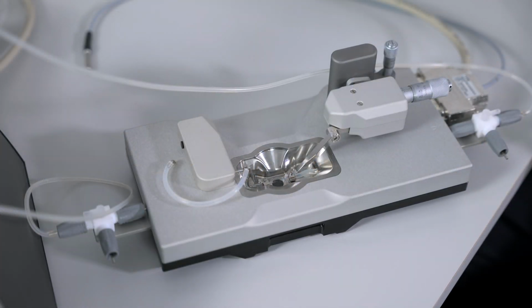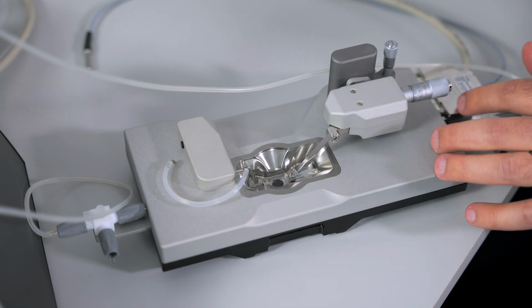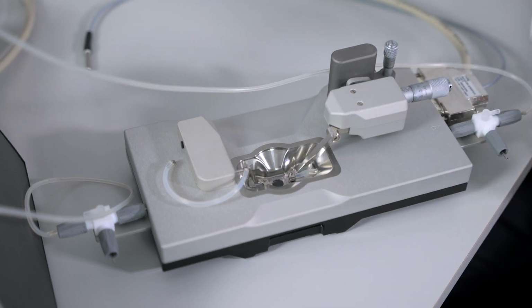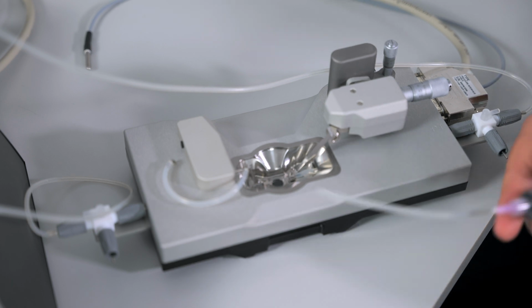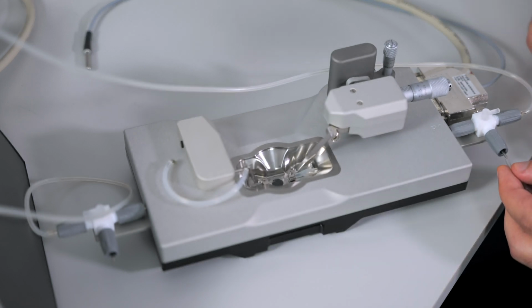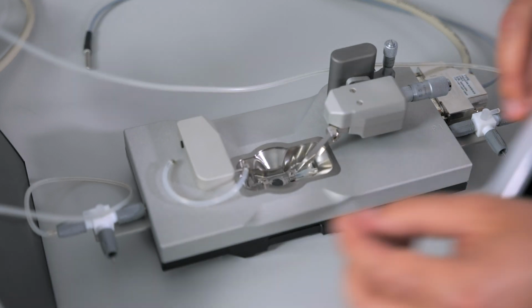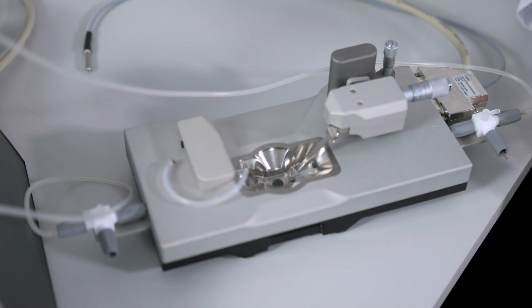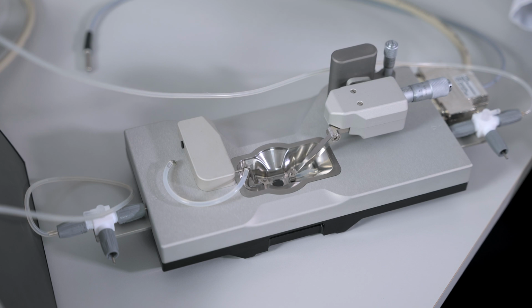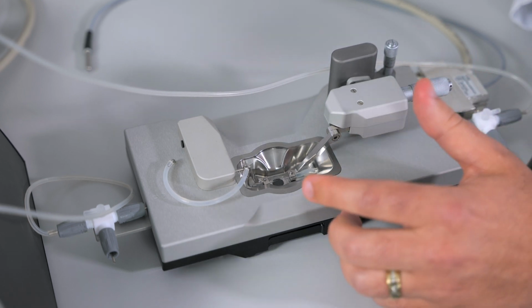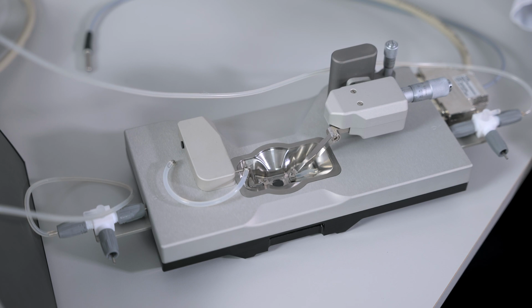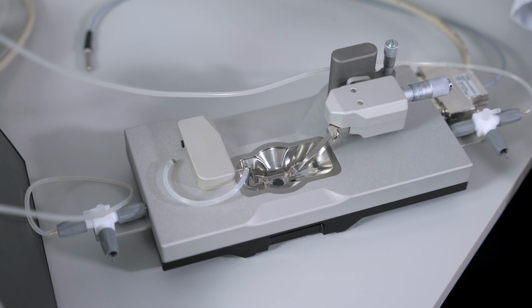When maintaining the pressure transducers in the glass cannulas, we will follow the procedure that was listed earlier. You want to make sure that the interface is powered on and connected with the myograph cable. You can take a syringe with the blunt needle tip and tubing connected to the P1 three-way valve as well as the P2 three-way valve, and apply either 8% acetic acid or distilled water through your lines. Again, you will need to monitor the actual pressure that you are adding, as you can easily exceed the 200 and 250 millimeters of mercury of pressure.